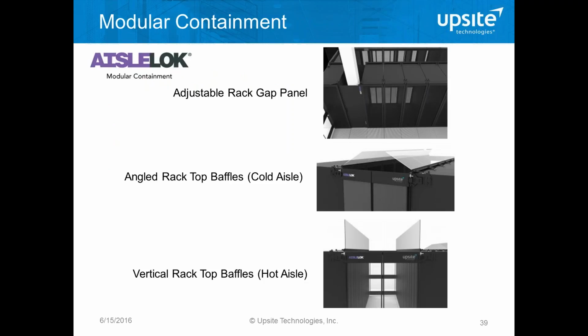So here are a few of the other products that we've developed to manage airflow at the row level. We have the adjustable rack gap panel. That's an adjustable panel anywhere from like 6 inches to 60 inches to fill the spaces between cabinets. And then we've developed baffles for both cold and hot aisle applications that prevent air wrapping over the tops of the cabinets. It's not full containment, it's modular or partial containment, and it creates enough of a blockage that the supply air can be balanced with the demand air of the IT equipment without getting into all the hassles of fire suppression issues that you deal with when you put a full roof on top of the cabinet.